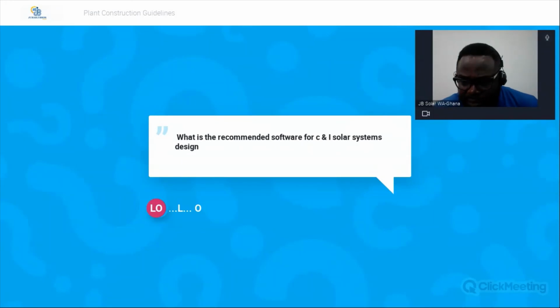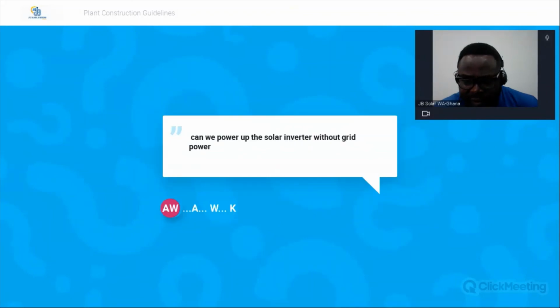More questions, let me take one or two more. Aga asked, can we power up the solar inverter without grid power? No. All the Huawei inverters I showed today are all grid tied, so they only work when the grid is available, unfortunately. They will work with generators if you have a hybrid panel as part of the system. Then if the grid goes off and the genset comes on, the genset can serve as the grid and the system will work. But if you don't have a hybrid panel, then they are purely grid tied.